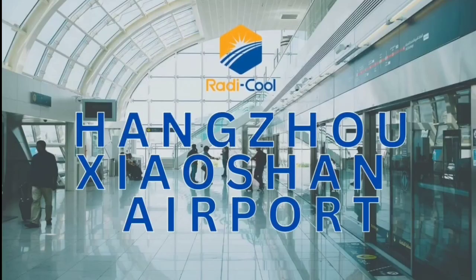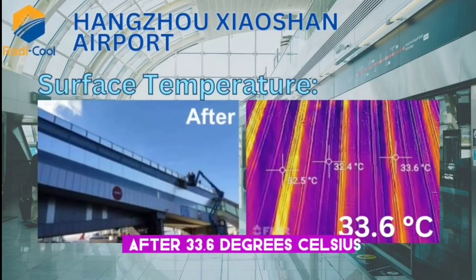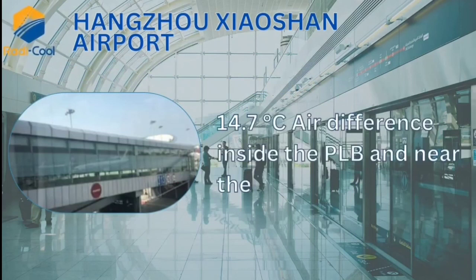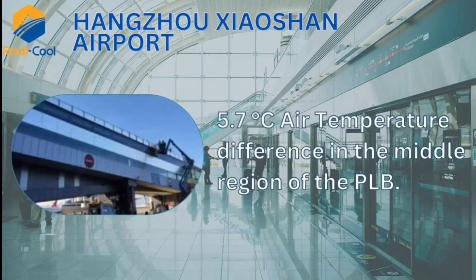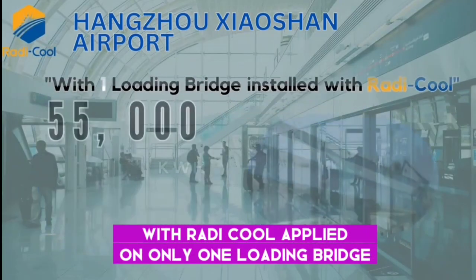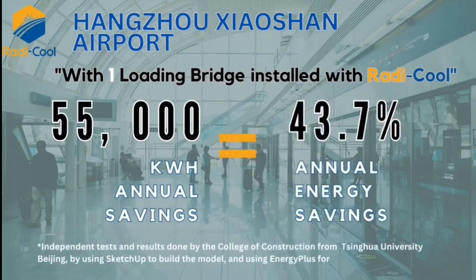Hangzhou Xiaoshan Airport, surface temperature. Before, 62.4 degrees Celsius. After, 33.6 degrees Celsius. 14.7 degrees Celsius air difference inside the PLB and near the glass. 5.7 degrees Celsius air temperature difference in the middle region of the PLB. With Radi-Cool applied on only one loading bridge, the airport achieved 55,000 kilowatt-hour annual savings, which translates to 43.7% annual energy savings.